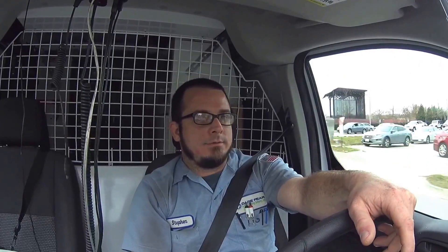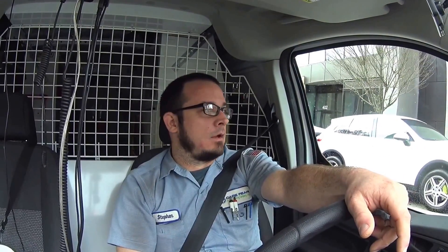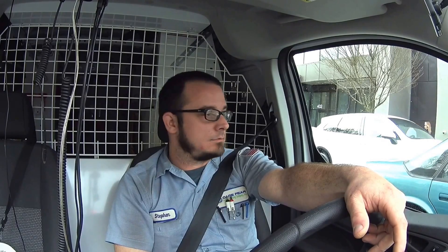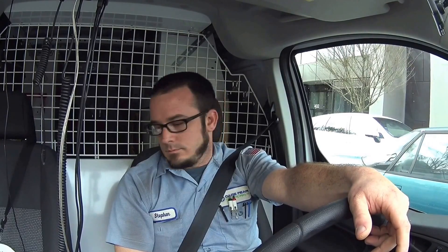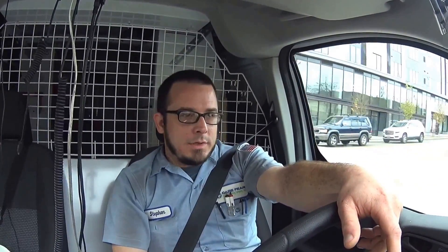Good morning YouTube. We're gonna try to get some footage for you. Apparently there was a diagnostic on this furnace by another company that the heat exchanger was cracked. One of our other senior technicians went out and said that he was wrong — that the secondary heat exchanger was blocked. There's a service bulletin from Carrier regarding this line of serial numbers that there's a potential for problems or some kind of a recall on it.